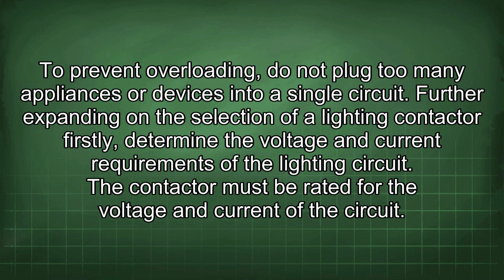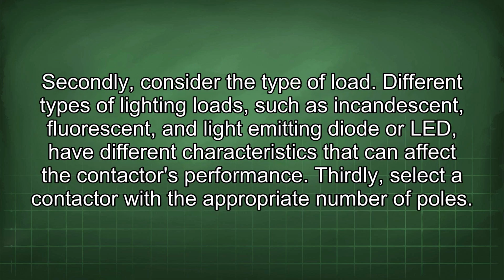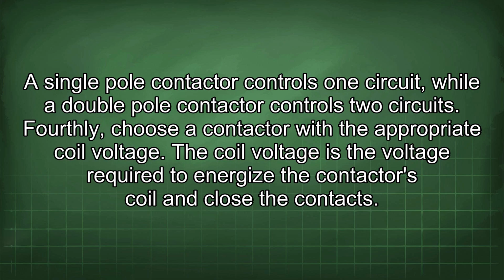Further expanding on the selection of a lighting contactor, firstly, determine the voltage and current requirements of the lighting circuit. The contactor must be rated for the voltage and current of the circuit. Secondly, consider the type of load. Different types of lighting loads, such as incandescent, fluorescent, and light-emitting diode or LED, have different characteristics that can affect the contactor's performance. Thirdly, select a contactor with the appropriate number of poles. A single-pole contactor controls one circuit, while a double-pole contactor controls two circuits.